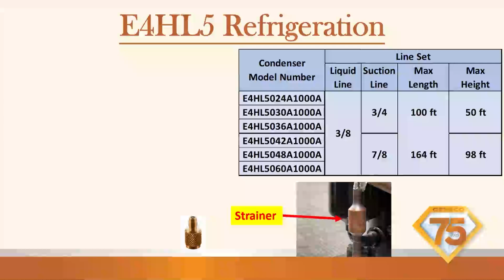So I was trying to tell the technician on site, this is a brand new piece of equipment, and we had a plugged strainer in the outdoor unit. I said, hey, why don't you just go ahead, cut that strainer out, straight pipe it with some 3/8 and put in an external liquid line dryer. And the homeowner refused and wanted a new unit. We could not give them a new unit because that was an installation error. They did not use nitrogen while brazing. It was documented on their startup report. The homeowner was right there. They had to eat the cost of the unit.